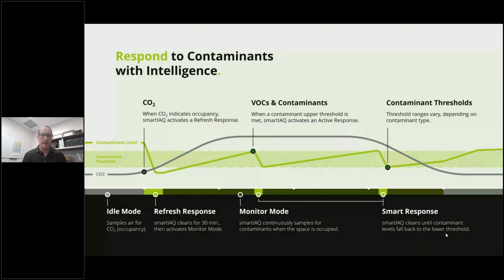Okay, so how does our system operate? Well, if you did not want to tie this back to your BMS system through BACnet or Modbus, we can operate independently. We put into the intelligence of the unit a manner by which it can operate on its own. If you start on the left here, you'll notice idle mode, where no one's in the room. It's going to notice that the CO2 is at background, or basically equal to outdoors, and it will put itself into an off position where it kicks on every 5 minutes and will measure the CO2 in an effort to see if CO2 has risen. As soon as it notices somebody's in the room through the proxy of CO2, it will kick itself into a refresh response. That's a cleaning process by which it will immediately get the room ready and really clean that space to get good air quality to get started for the day.